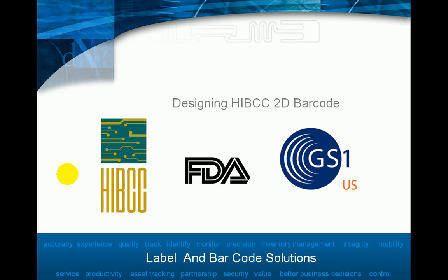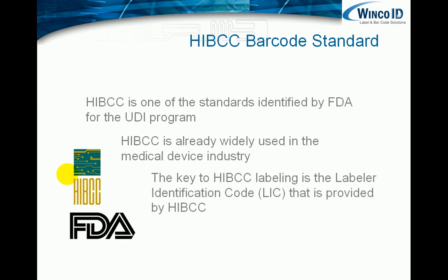In this case, we're looking at using 2D barcodes in the HIBCC system. The Health Industry Business Communications Council has a range of barcode standards that are used strictly in the medical and medical device industry, very widely established there. And it is one of the standards that's been identified by the FDA for their UDI program.